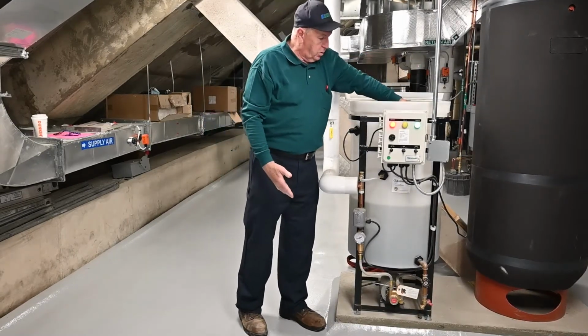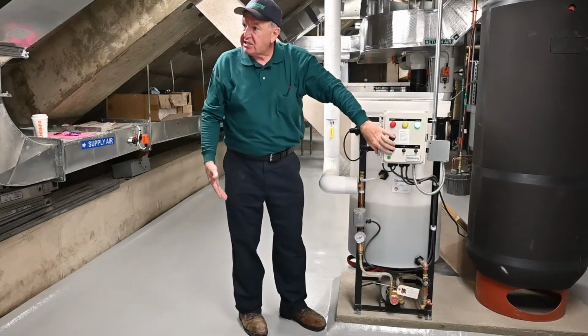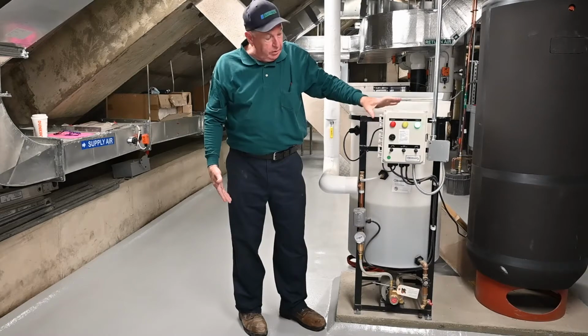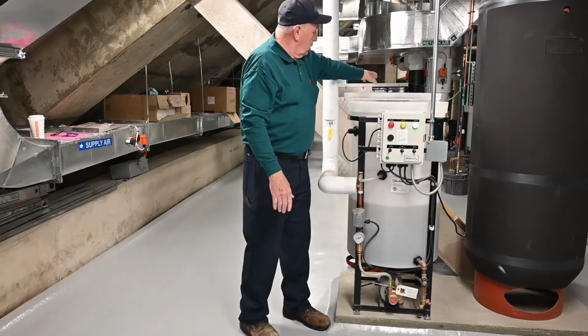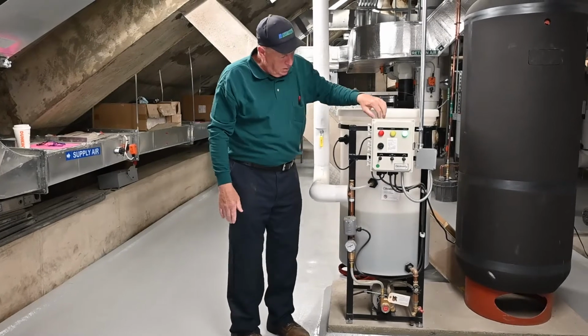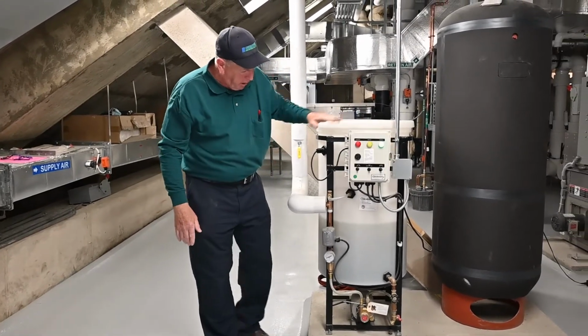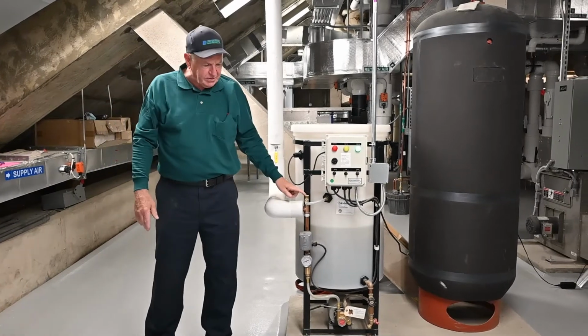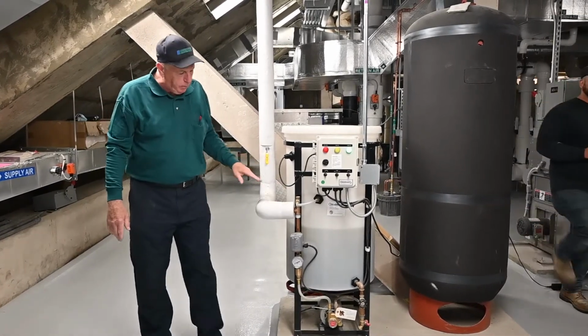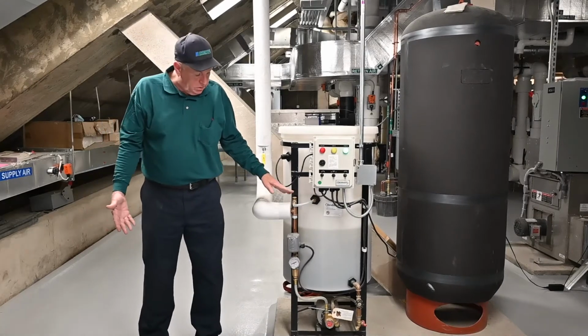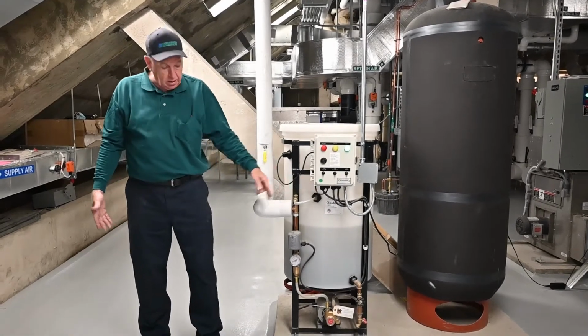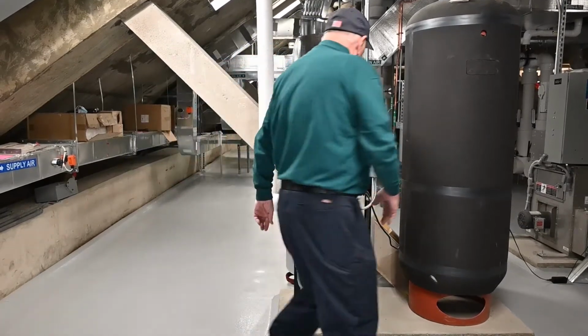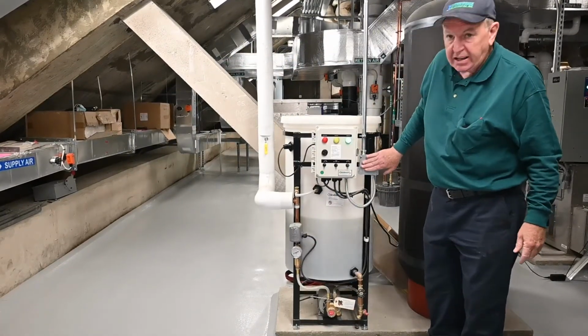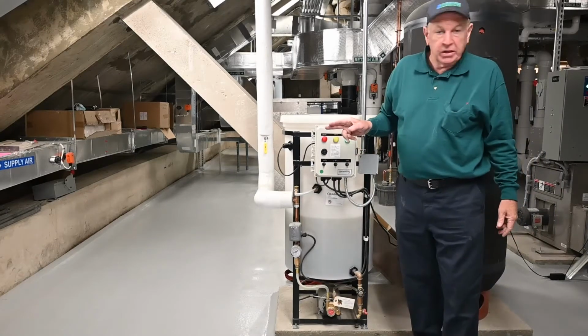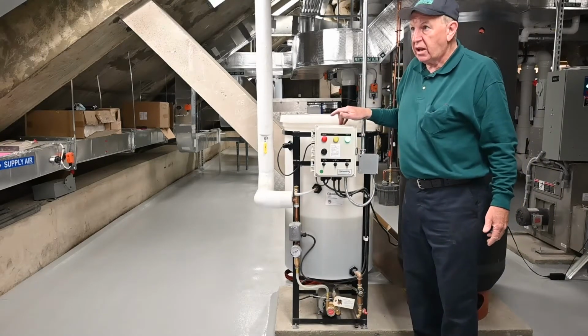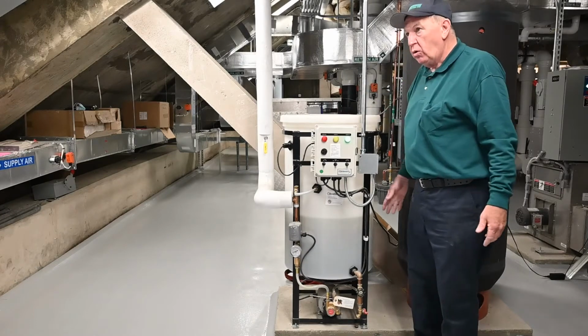So even though you silence the horn, the alarm is still on. So typically those three switches stay to the right. And this is a relief valve. So if there was a blockage somewhere and this pump was making 40 pounds, then this relief would just dump it back in the tank. I believe this is tied into the EMS, so if the alarm goes off, the building management system will know that there's an alarm. So if the level gets too low, you'll get an alarm.